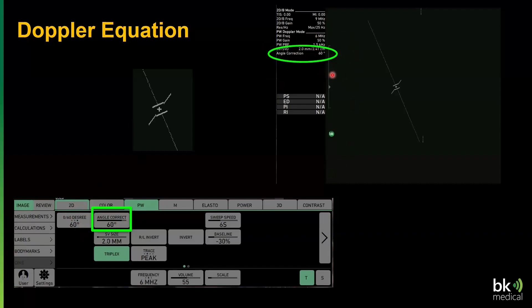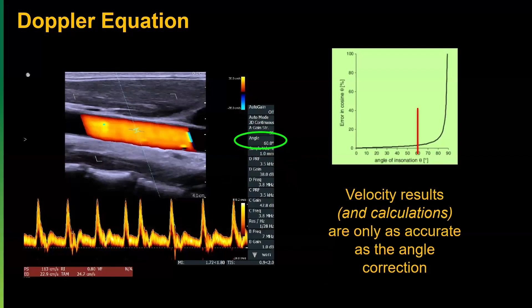And again, for today's visit, I'm going to say 60 degrees or less will keep you out of trouble. What I mean by that is that your velocity measurements will be considered accurate. They're only as accurate as the angle correction. So it looks good here, yes. And then I want to glance over here or somewhere on my display, depending on your system, to confirm that that angle is 60 degrees or less. And again, that's going to be critical for the accuracy of the measurements.